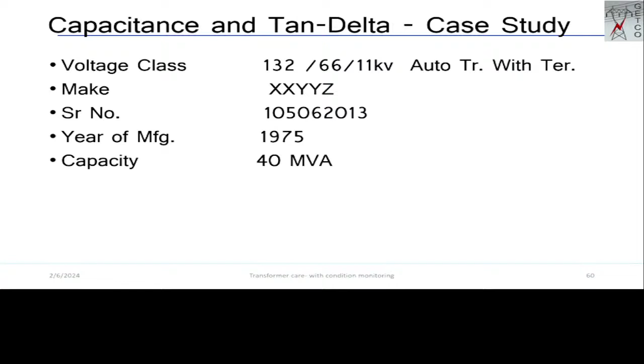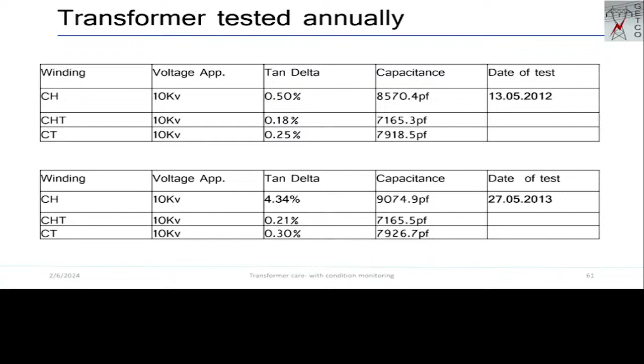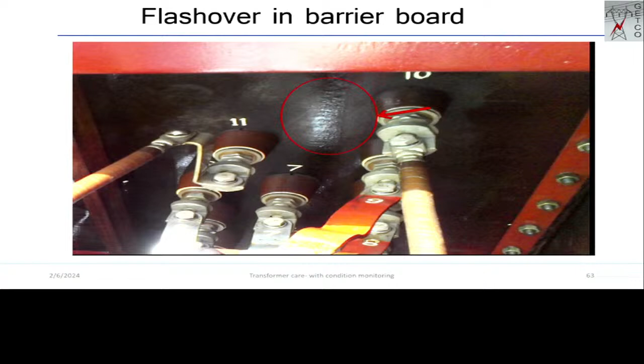Each and every year we regularly measure the capacitance and tan delta test. So this is the 132/66 kV 40 MVA transformer. At the routine annual test, we observed that only in the CH winding the tan delta had increased. The other two windings' tan delta was normal. Okay. So in the HV winding there is an HV bushing and OLTC. We checked the tan delta of all the bushings, yes it's okay, and checked the BDV of the OLTC oil, it was found okay. So it was decided to inspect the transformer.